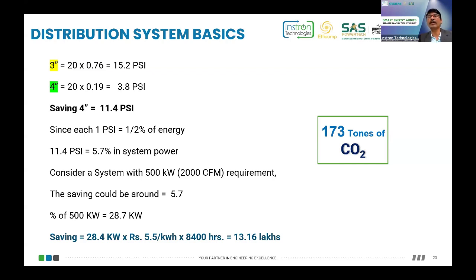And there is a basic thumb rule in compressor systems that for every 1 bar excess pressurization, that is 14 psi, compressor power increases by 7%. So in correlation to that, the 11 psi increase which may be required with a 3-inch line would cost you around 13 lakh rupees in a year. So who was smarter? The purchase guy who saved 6 lakh rupees initially by selecting a 3-inch line in place of a 4-inch line, or a person who has installed a 4-inch line and then saves 13 lakh rupees year on year.